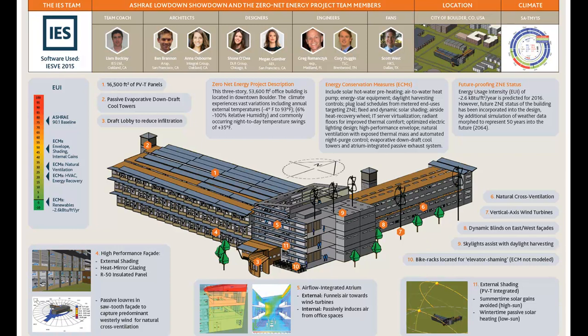Those are definitely really close energy-use-wise. It came down to the fact that radiant floors gave us better thermal comfort in the design, and also really allowed us to take advantage of the low return water temperatures that we get from having a solar thermal system built into our PVT panels.